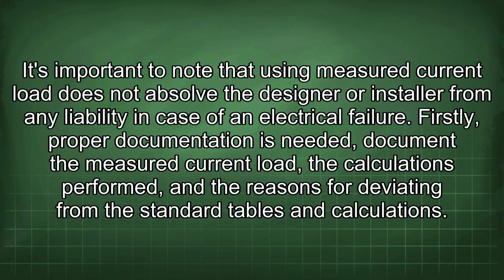It's important to note that using measured current load does not absolve the designer or installer from any liability in case of an electrical failure. Firstly, proper documentation is needed. Document the measured current load, the calculations performed, and the reasons for deviating from the standard tables and calculations.